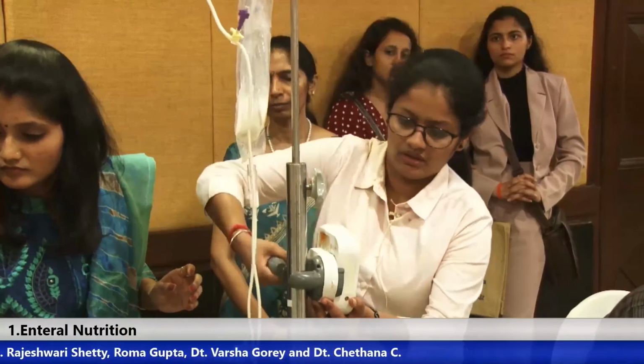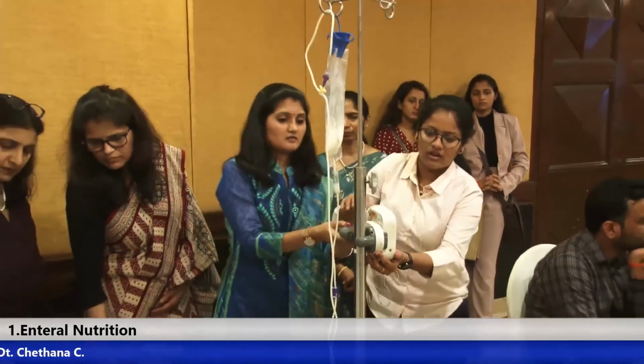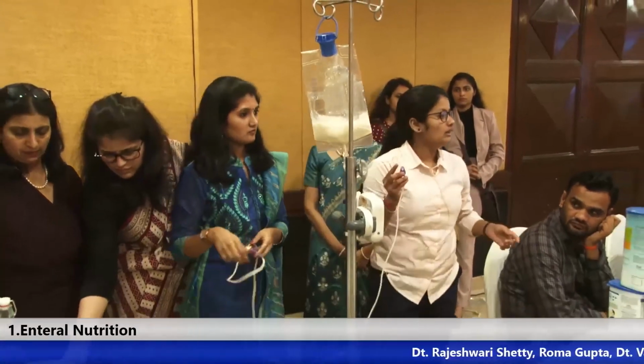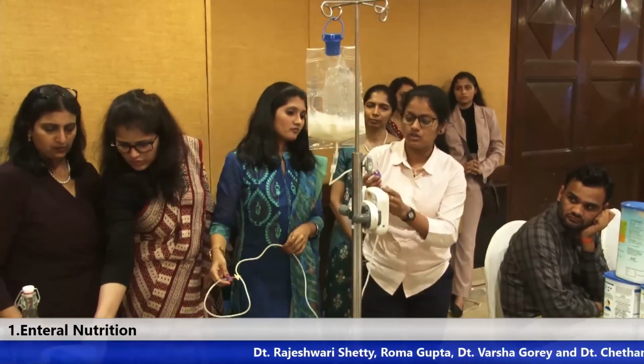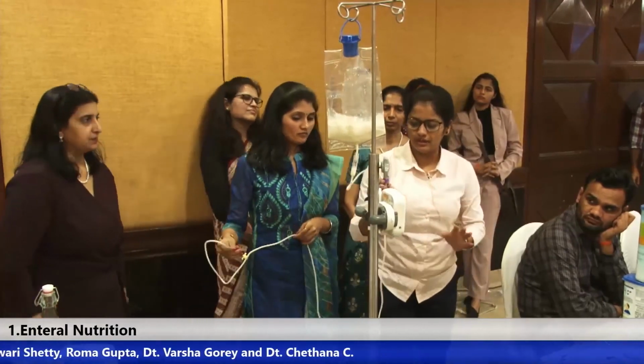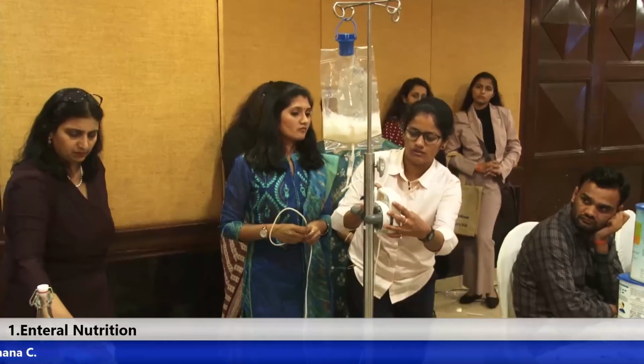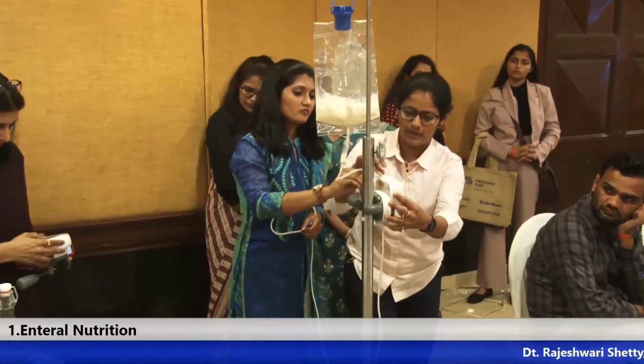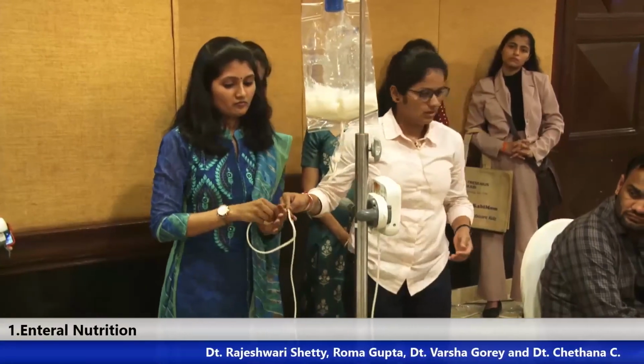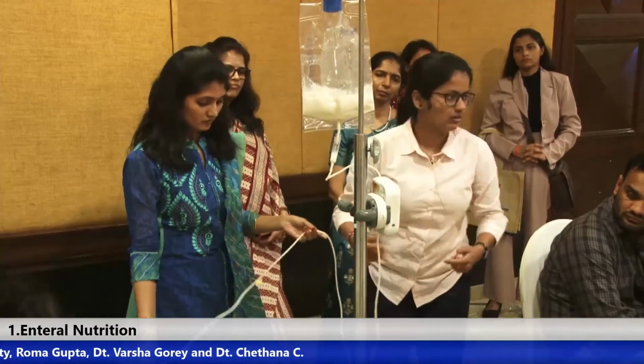Okay, you have to press the on button for 3 seconds and it will start. Then next, you have to align this tube. This is a purple colored clamp, patented for this pump only. It goes with this bag only. So you have to push like this, align the bag and close the door. Okay, and we have done priming. Here you can do automatic priming through this button, but we have done it manually.